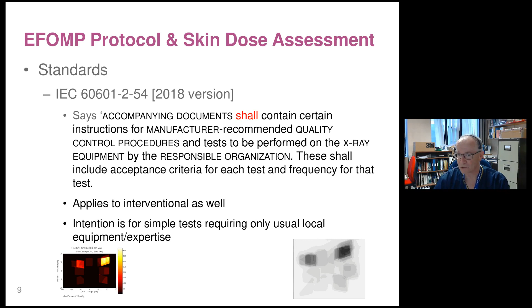What does the protocol actually say? Well, for acceptance testing, it says if there's a manufacturer protocol, then follow it. And we've already seen that's a bit of a dream at the moment. So how are you going to do it otherwise? Well, there are various ways you can do it, but essentially you're going to have to put something on the table, irradiate it, make measurements, and then see how well they compare to the model, not real world, but the model that displayed. So for a PA projection, you just put a block of something on the table.